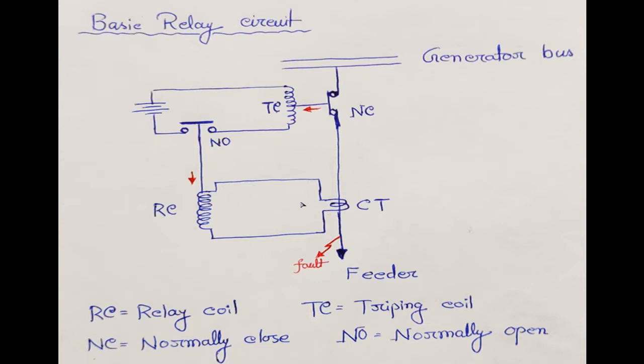The relay is actually sensing the fault. After sensing the fault, it generates a trip signal, and the trip signal goes to the circuit breaker. The circuit breaker actually controls that switch. So this is called the basic relay circuit. This is the relay coil, RC means the relay coil. TC means the tripping coil. This is the normally closed switch. It will open automatically in case of a fault, and this is the normally open switch, and during the fault this switch becomes closed to complete the tripping coil circuit.